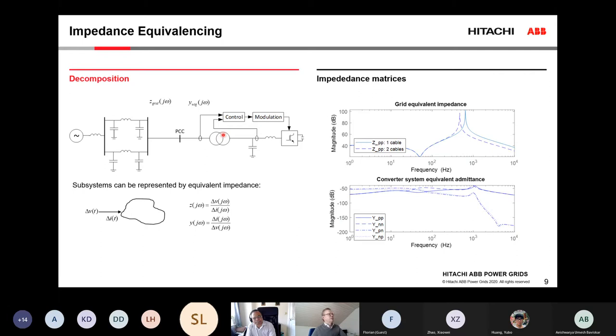And that gives us this representation, where the impedance is basically the transfer function modeling how the grid responds to a small, incremental current injection, and what incremental effect that would have on the voltage. And the other way around for the admittance, where we would be thinking about applying a small voltage perturbation and seeing how the current would change. And those can be represented by impedance matrices.